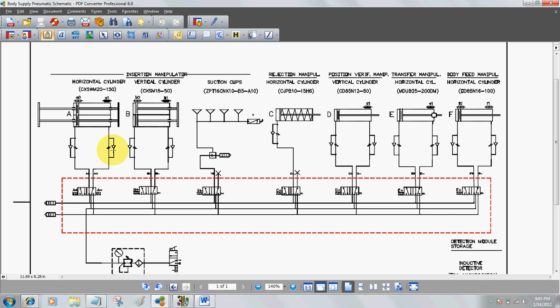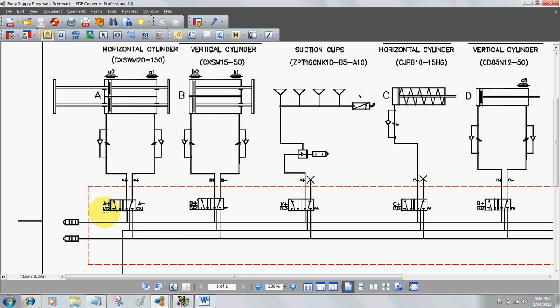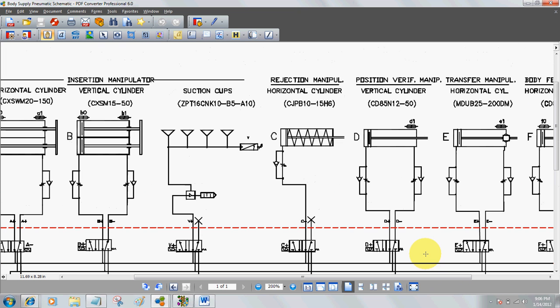These devices are flow controls, which allow us to meter the amount of air going out of the cylinder. These are our valves — it's important to understand how they operate. Some valves have two coils, indicated by two boxes with slashes on the ends, so it takes a signal to both extend and retract. Others have only one coil, so you initiate a signal to extend the cylinder and the absence of that signal automatically retracts it. The same applies to the horizontal cylinder: air extends it and removal of the air signal forces it to retract.